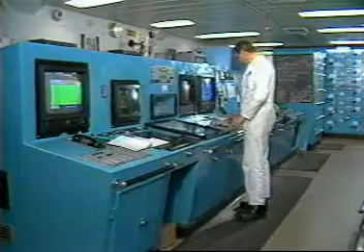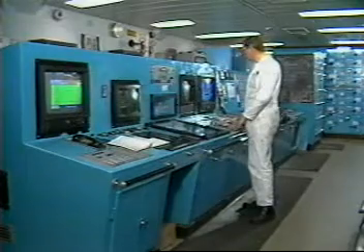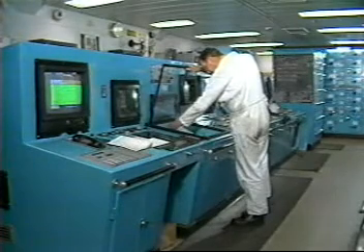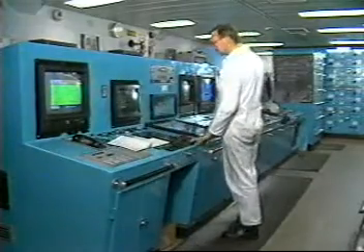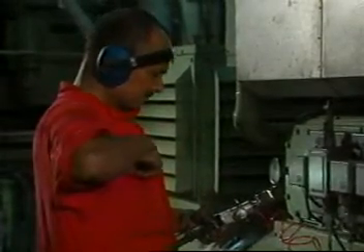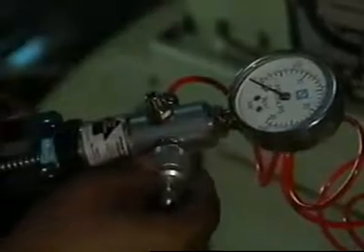The alarm setting can usually be read from the central monitoring system, provided that it can be demonstrated as operational. This is done by resetting the alarm to a normal value or by simulating an alarm value. But the most convenient method for this test is the use of a test pump and gauge. Here, a lube oil inlet pressure sensor is tested with a precision testing instrument.